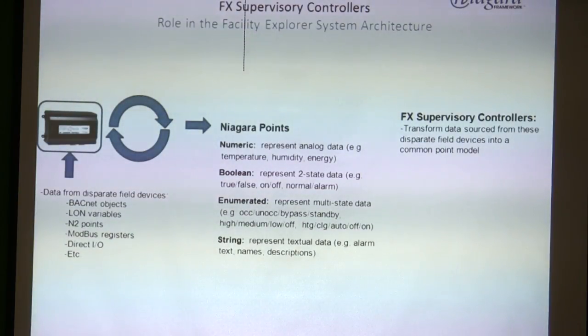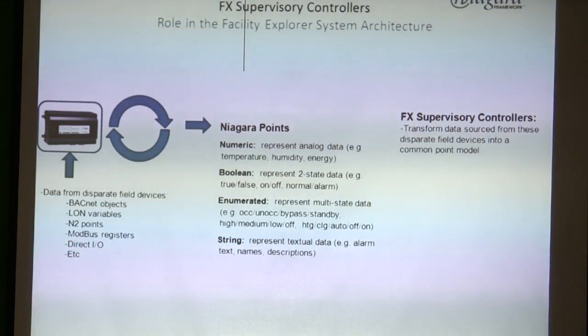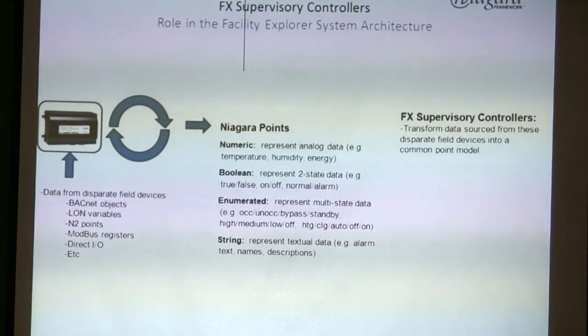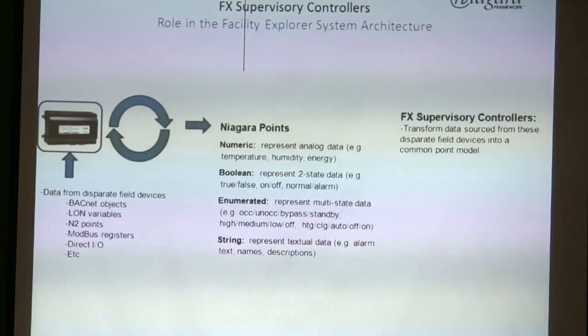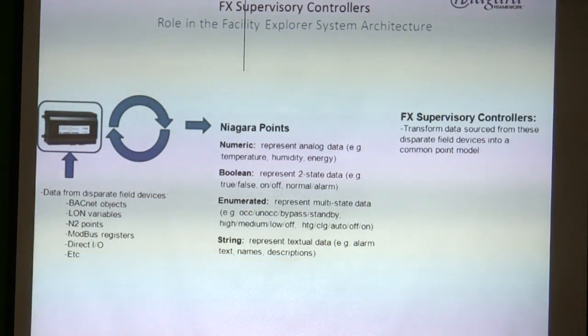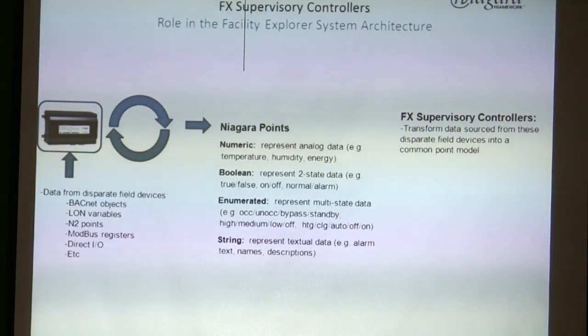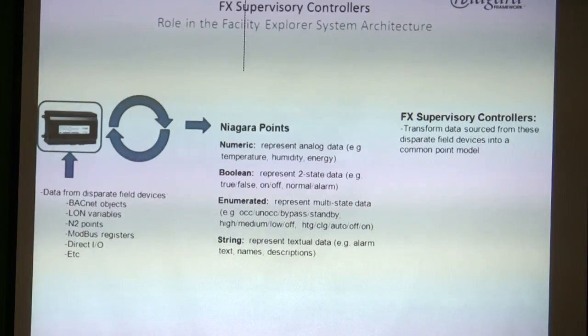This is important if you're getting into programming: there are different point types — numeric, boolean, enumerated, string, and two of each. So if you had a BACnet VAV controller with a setpoint, that would get pulled up into the Jace and turned into a numeric writable point.